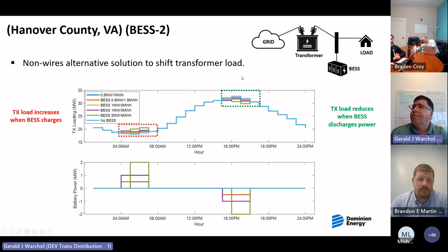This was a very proud moment for the Grid Solutions engineering team when we had our first peak shaving event during the morning of 11/17. We were forecasting a 28 megawatt peak on the transformer at Hanover substation, so we made sure the energy storage system was charged up and ready to go. We forecasted that peak and had it start to discharge, removing the top portion of it. This graph shows the battery started discharging at 6:31 a.m., completely discharged, and successfully removed the peak on the transformer.